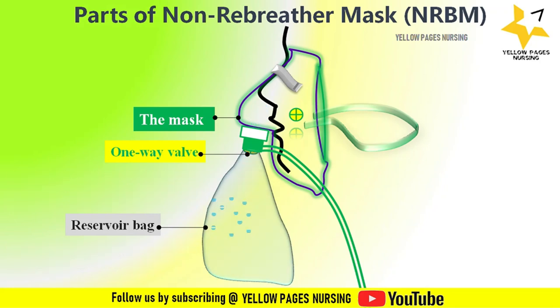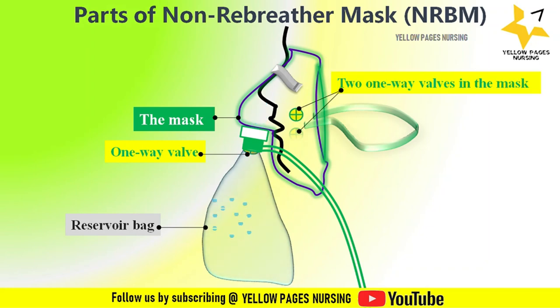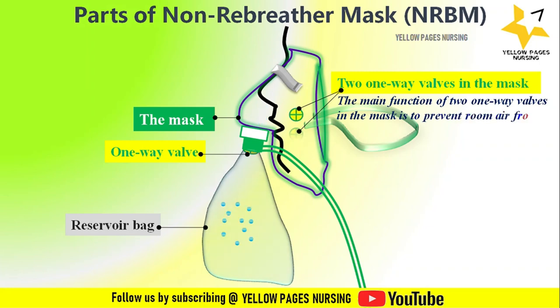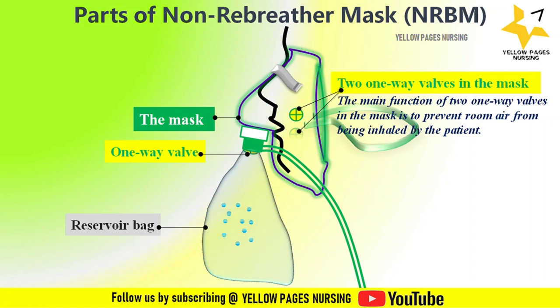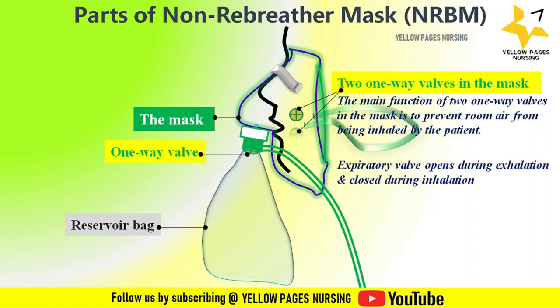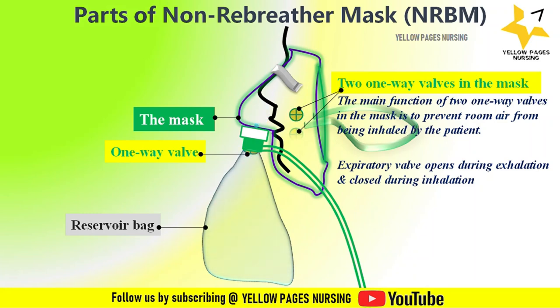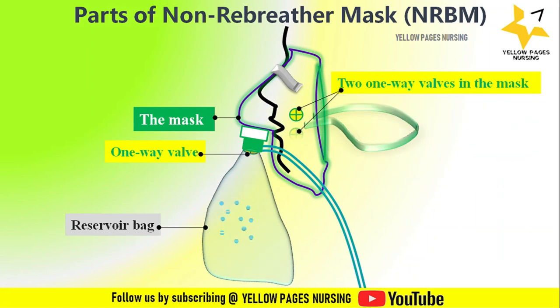The mask also has two one-way valves, called expiratory valves, one on each side of the mask. Their main function is to prevent room air from being inhaled by the patient. The expiratory valves open during exhalation, allowing exhaled air to escape from the mask, and close during inhalation, thereby preventing the patient from rebreathing the exhaled air.